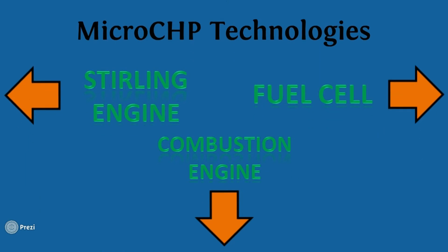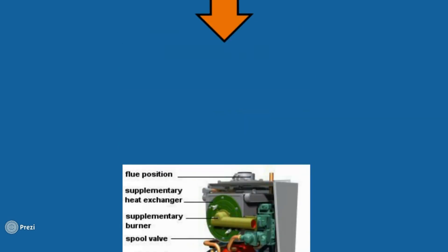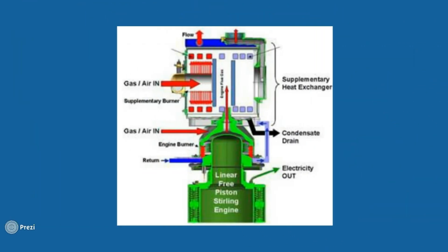At present, there are three major types of micro-CHP. Firstly, internal combustion engines. These are characterized by constant heat and electrical output. The predominant fuel used is natural gas and it operates either by compression or spark ignition engines. Secondly, Stirling engines. The operation involves a moving piston encased within a cylinder, releasing mechanical energy due to pressure changes. It offers stable combustion, reduced maintenance and a high selection of fuels.